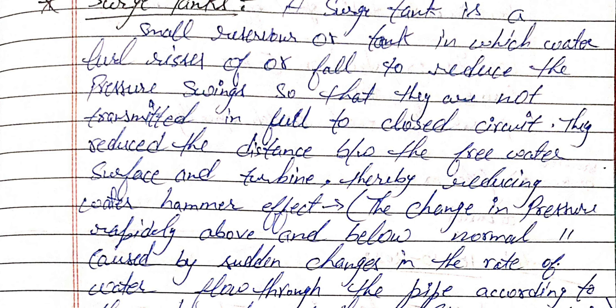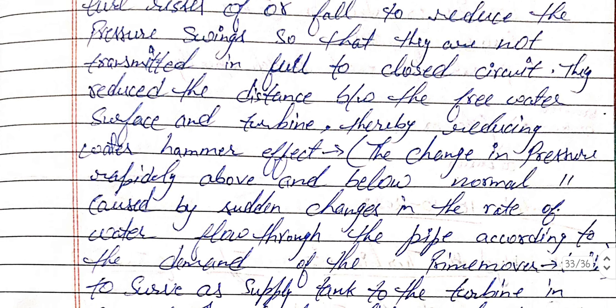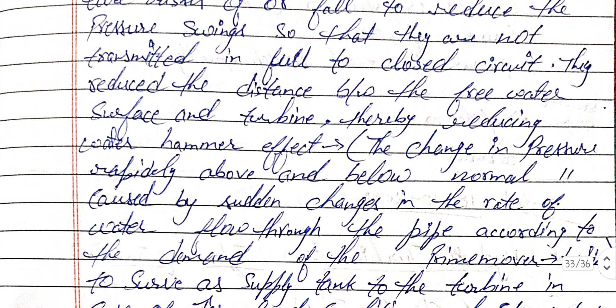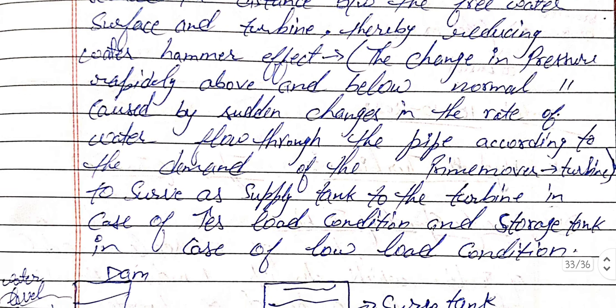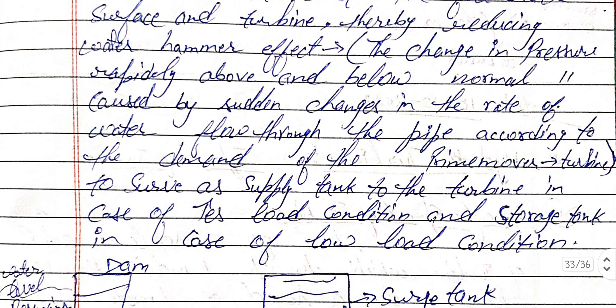The water hammer effect refers to the change in pressure rapidly above and below normal pressure, caused by a sudden change in the rate of water flow through the pipe according to the demand of the prime mover — the turbine. The surge tank serves as a supply tank to the turbine under increased load conditions, and as a storage tank under low load conditions.